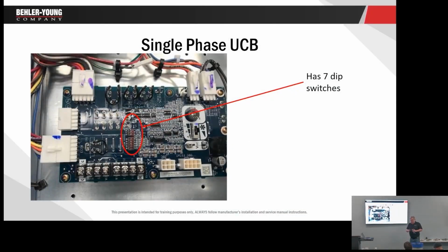Remember when I said we have a standard static, a medium static, high static? Those dip switches tell the single-phase unit what blower's in it. So simply put the dip switches back to the way the switches were on the old unit. Or if you look on the cover of the control compartment where your wiring diagram is, it'll show you where the dip switches go. So put them back. They're preset. Not with the replacement board, but in the unit, yes. So when the unit's delivered originally, yes, they're preset.